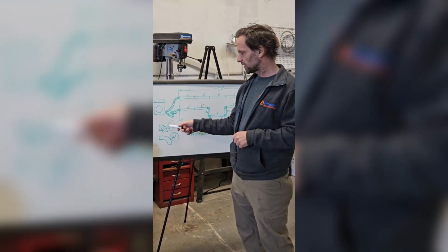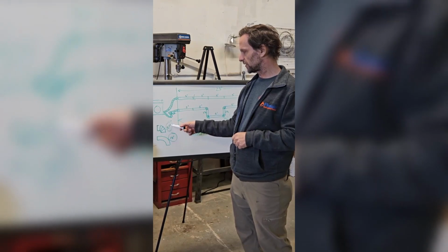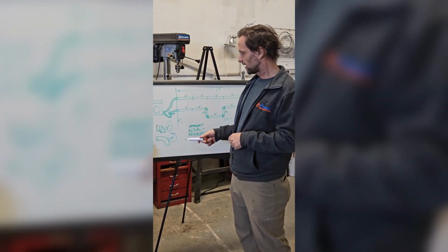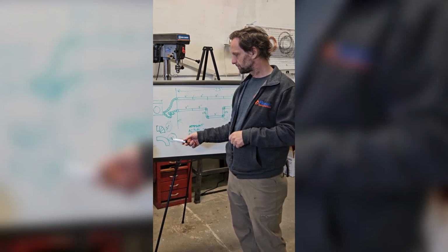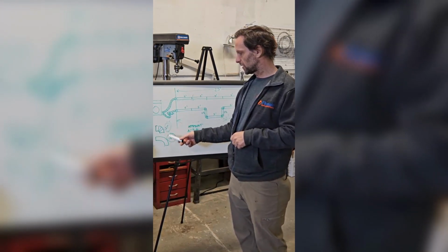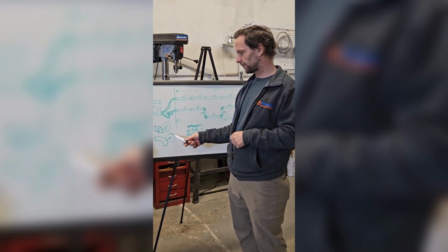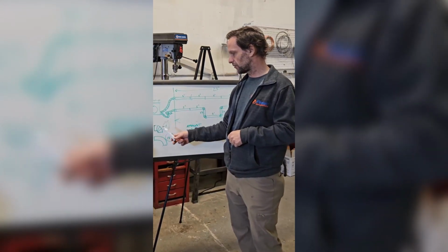So that means this little elbow is worth 5 feet of a straight run. Unlike that, the long radius elbow creates as much resistance as 1.5 feet. So that's a huge difference.